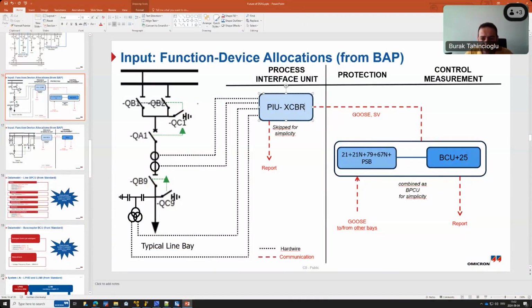And then this XCBR receives a GOOSE, which is a trip GOOSE, from the PTRC, the master trip information of any protection function logical nodes. Every protection function will initiate or trigger the PTRC, which will send out the GOOSE, maybe as a trip GOOSE. Then the XCBR will allocate it and eventually turn it into a binary output to trip the trip coil of the circuit breaker. So we would break up the logical nodes in this case. But for simplicity, as I said, I have taken the XCBR and put it in the BCU as well, together with the CSWI.